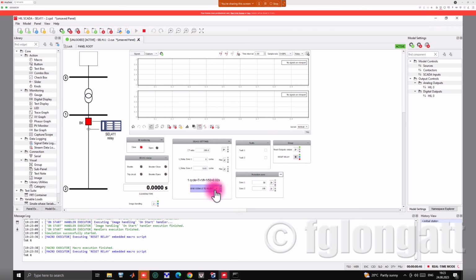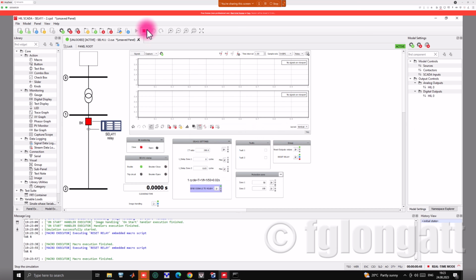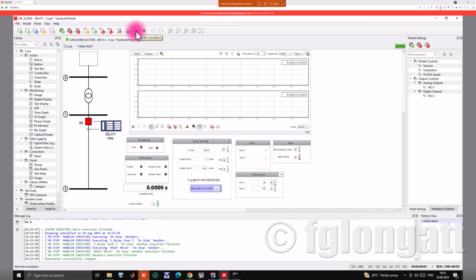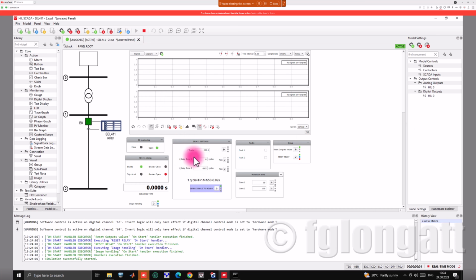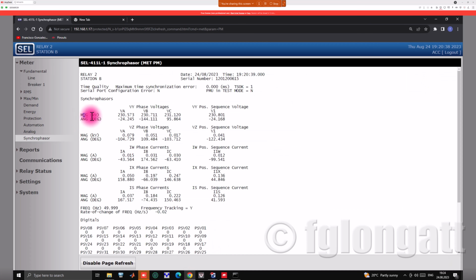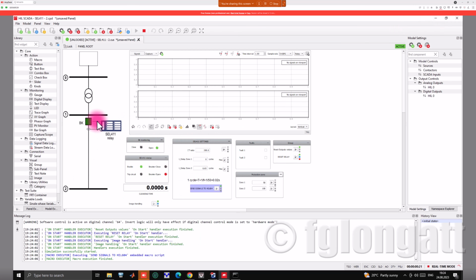Let me reset the relay, send the signals, and restart the simulation. Right now, let me send the signals to the relay. Over here you can see, voila, we have 230 kV going into the terminals of this relay, because the circuit breaker is open and we are receiving voltage from the voltage transformer.